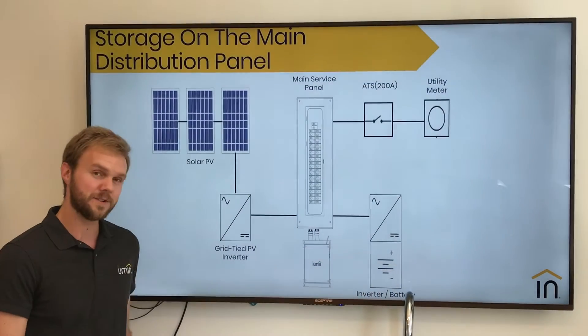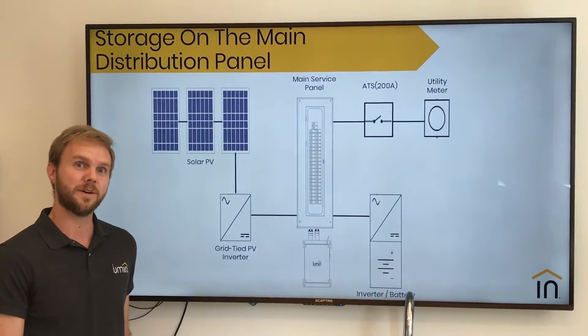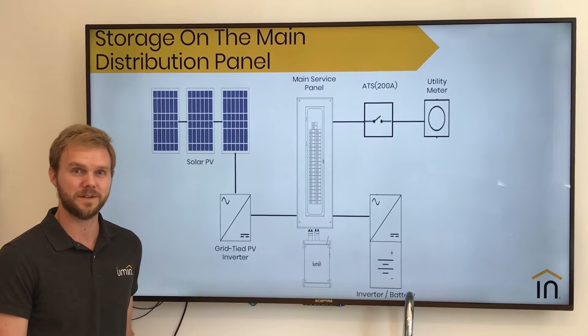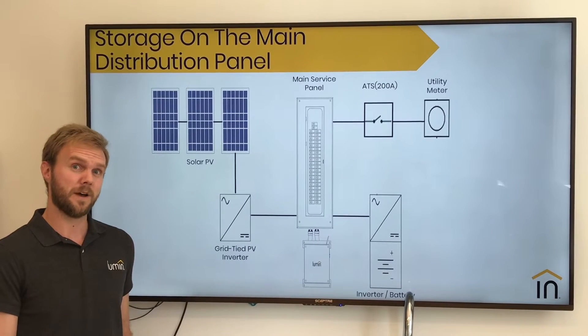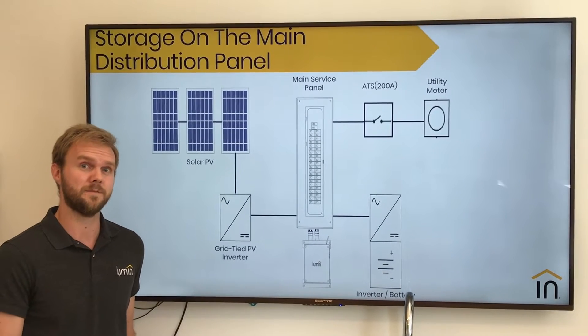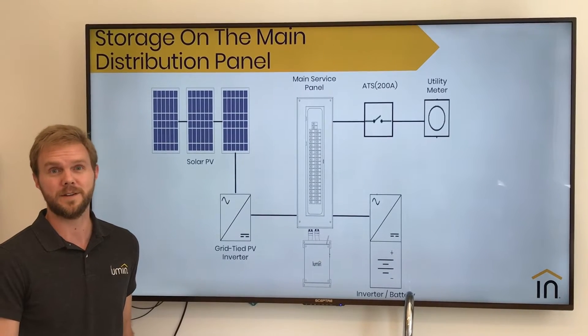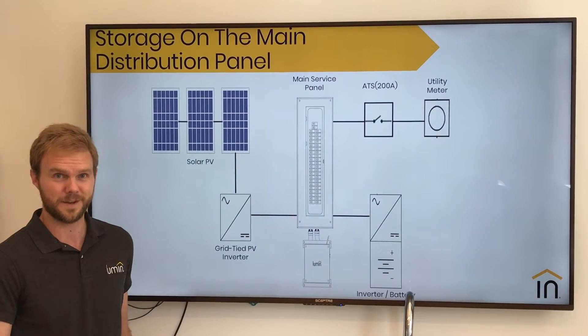The first configuration we'll talk about is solar on a main distribution panel with storage and Lumin connected on that same main distribution panel. We're starting here because this is the most popular configuration due to our off-grid mode and how it allows for dynamic and configurable backup. Many times, it eliminates the need for that PESP protective loads panel altogether.